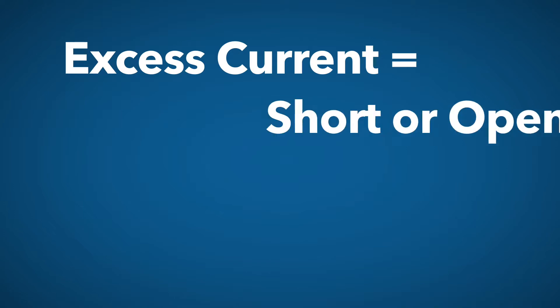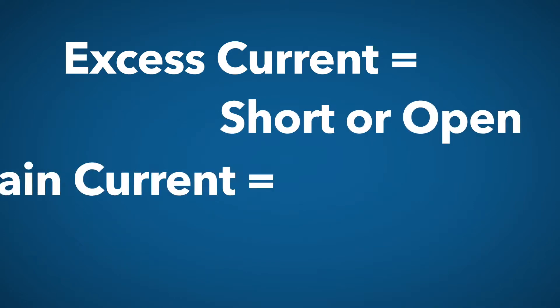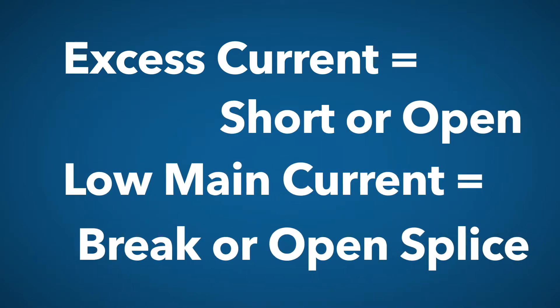Excess current will indicate a short or open. Low main current will indicate a break or an open splice. In the next section, we'll cover these in detail.